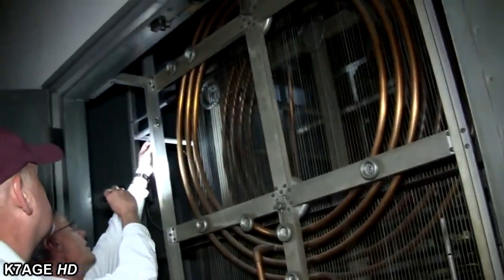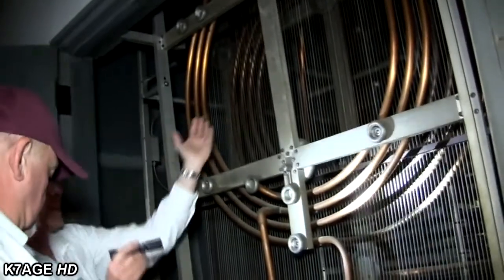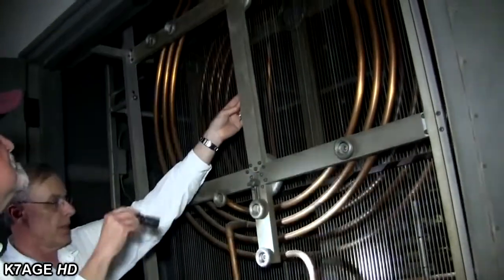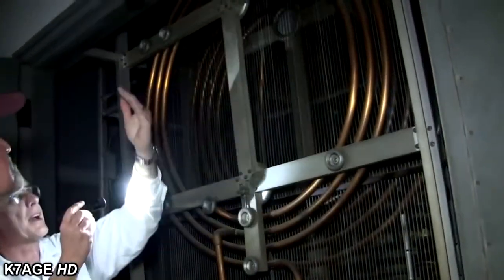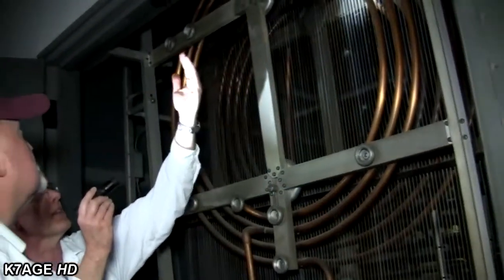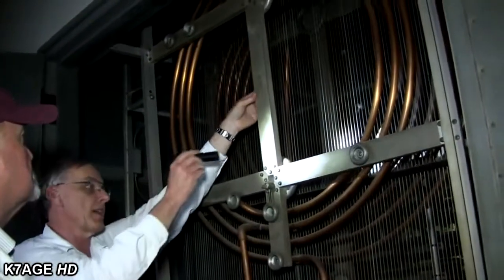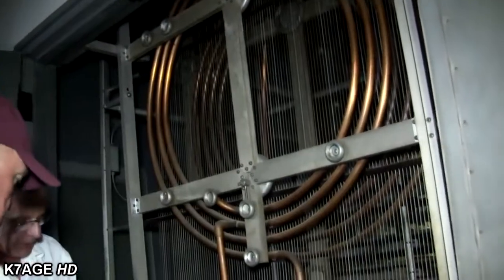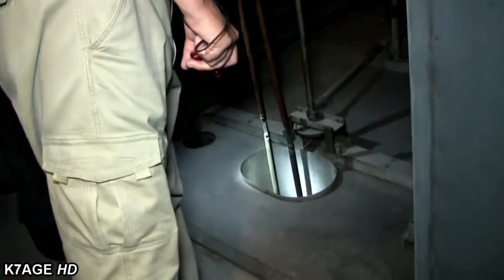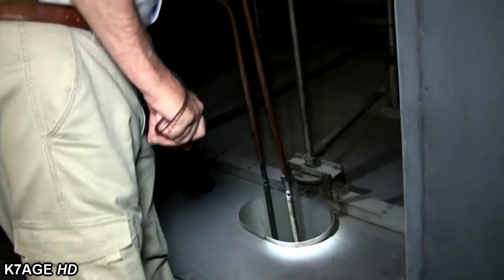This push rod here moves this section - this is the output coupling inductor. It moves back and forth, coming out this direction or moving back in closer, to change the output loading of the transmitter. The output from the transmitter are these two 3/4 inch copper pipes that go down into the switching mechanism underneath the floor there.